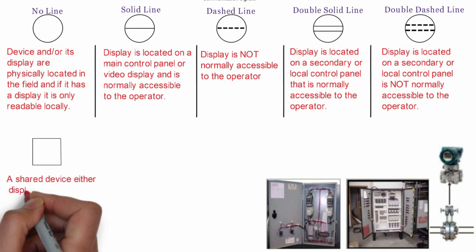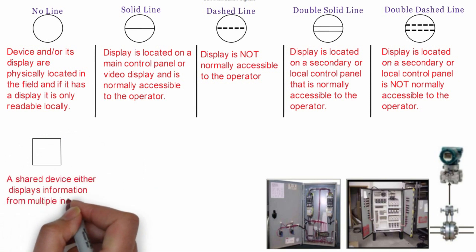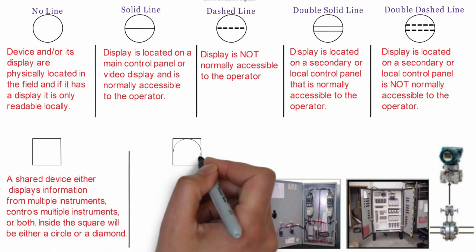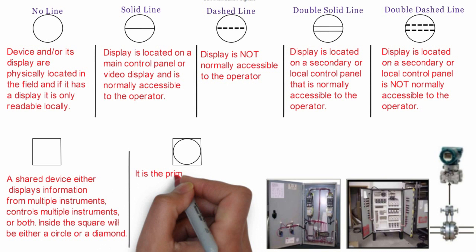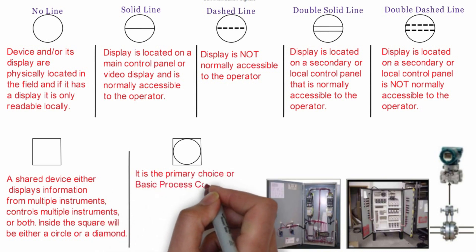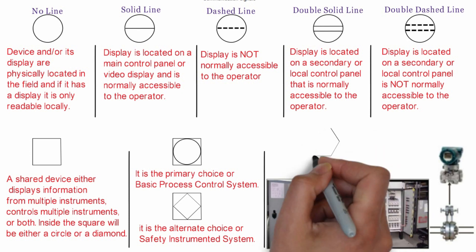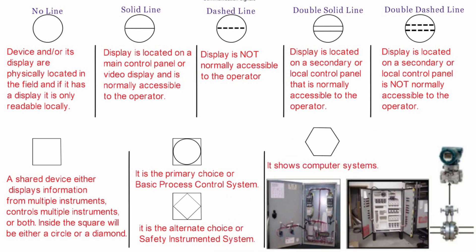Square bubble represents shared display. A shared device either displays information from multiple instruments, controls multiple instruments, or both. Inside the square will be either a circle or a diamond. A circle represents that it is the primary choice or basic process control system. A diamond represents that it is the alternate choice or safety instrumented system. Hexagonal bubbles represent computer systems. Circular bubbles represent discrete instruments.